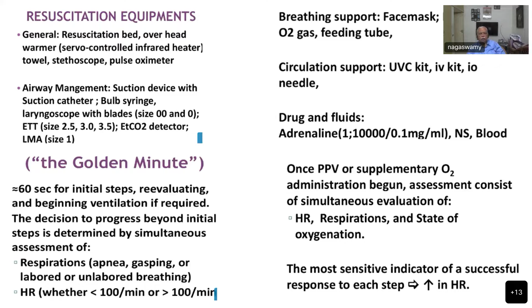So these are the pictures of those equipment which are required: radiant warmer, oxygen source, anesthesia, you have a neonatal resuscitator. The equipment name is resuscitator. It has an automatic airway pressure venting valve so that you don't blow out the lungs and cause damage. And it has a pop-off valve of more than 250 ml, suction, infant feeding tube, low pressure suction bulb, stethoscope, laryngoscope, ET tubes. Of course, this is a wrong picture with a cuff tube. You don't use a cuff tube. It is only a plain one. And transport incubator and ETCO2 monitor, which can be attached directly to the tube.